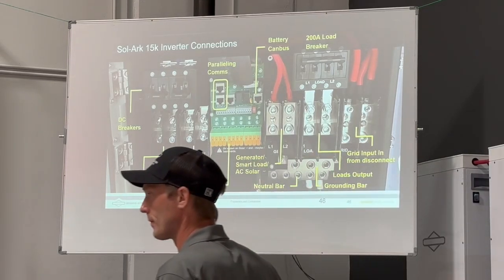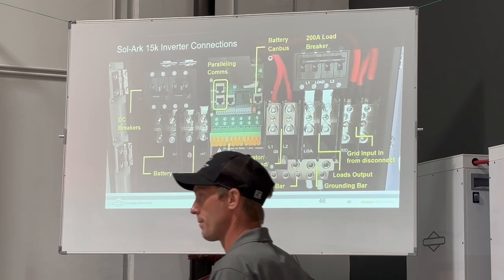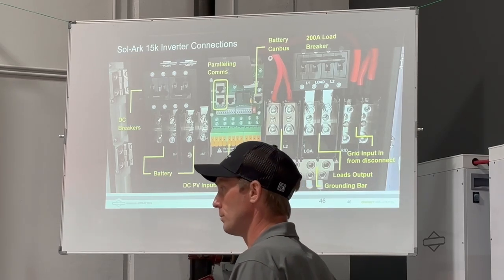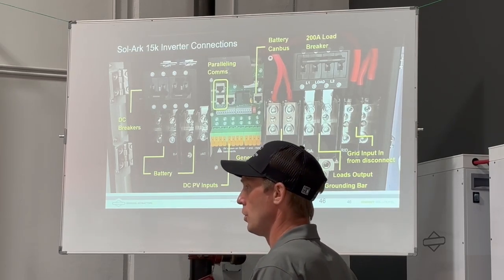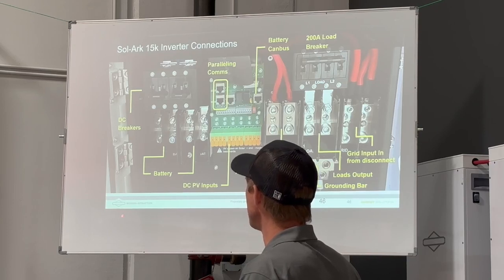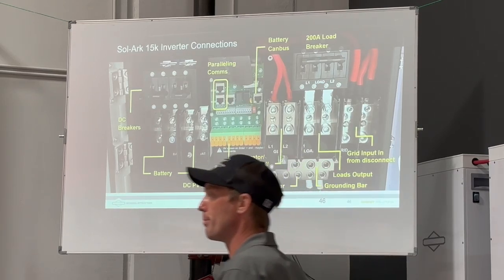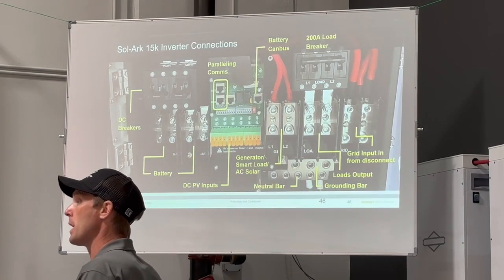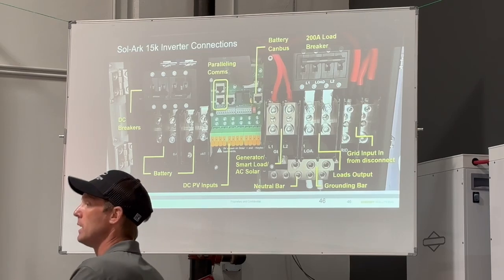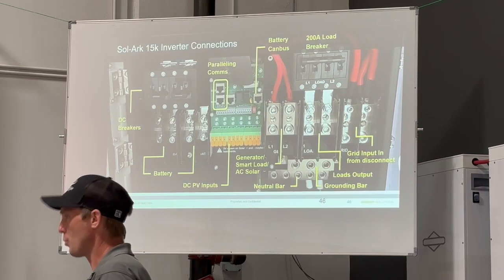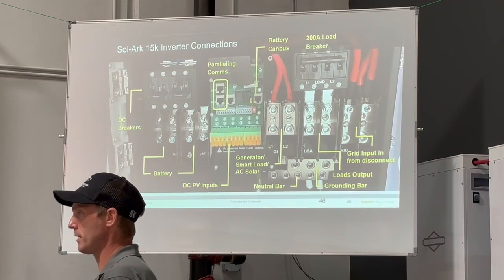You're taking your stack into one of your inverters. Talk about that connection to the other. Is it just a loop out for your DC battery? No, and you want to use common, so you would use a combiner, and you would come out of that combiner into both of the inverters. Equally. Right. Equally. And equalize your battery cable lengths if you can.